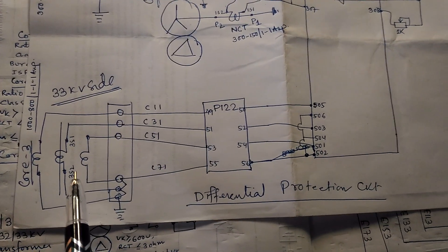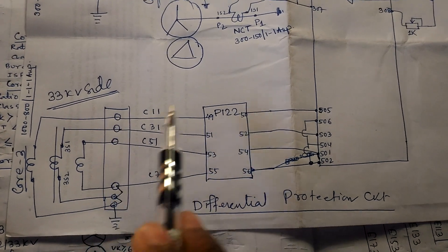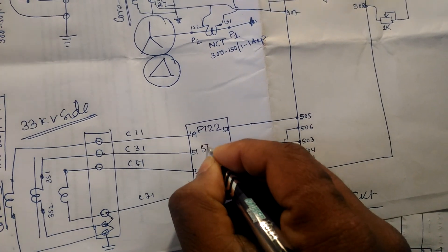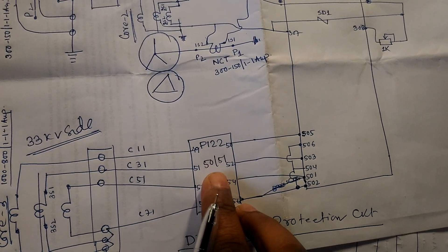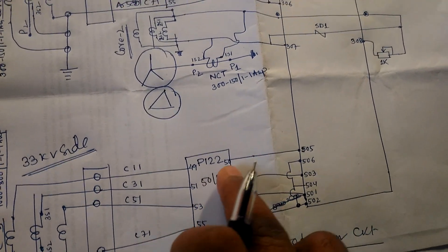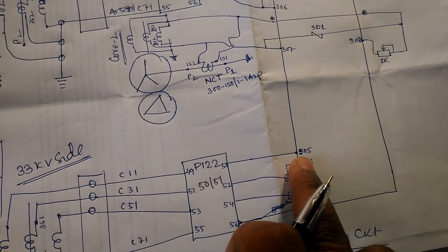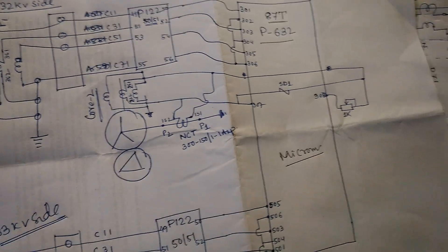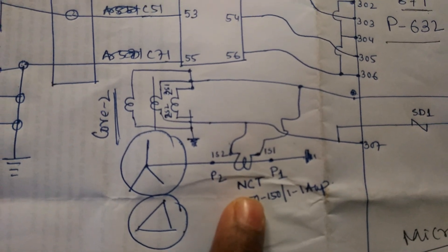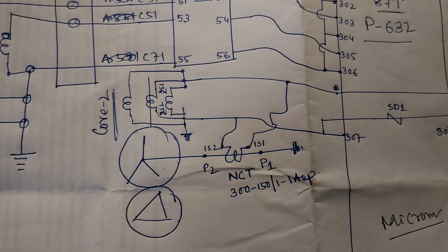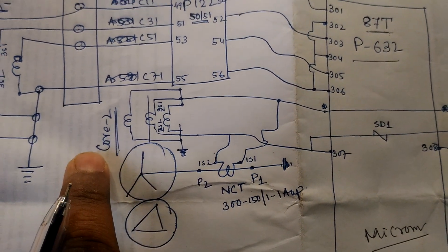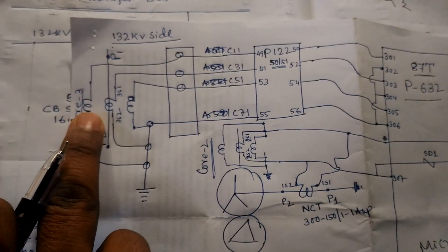The overcurrent and earth fault relay terminal is also connected to the 87T differential relay, as per this diagram. From the 33 kV side, the P122 relay (50/51) provides backup earth fault and overcurrent protection, and is also connected to the 87T relay. The transformer neutral CT is connected to core 2 of the main CT and then to the 87T relay. This completes the REF and differential protection circuit.